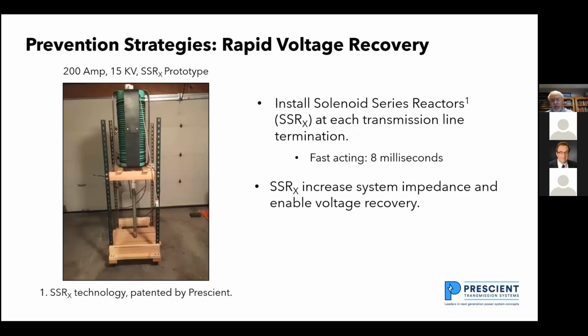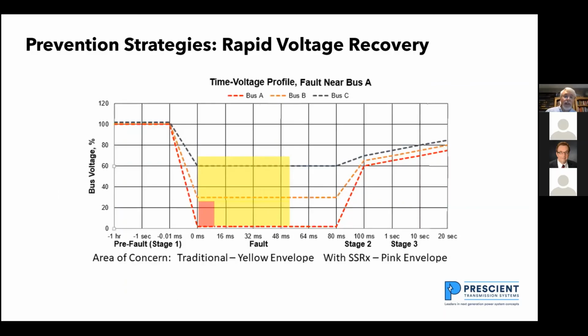Rapid voltage recovery is something else that's near and dear to us. When I look at rapid voltage recovery, I'm thinking of solenoid type series reactors. This is a prototype that we've built. This is a 200 amp 15 kV solenoid series reactor. And what happens is when these operate, they change the impedance of the power system, and they allow voltage recovery in 8 milliseconds. The fault is still on the system for 100 milliseconds, but the voltage recovered.